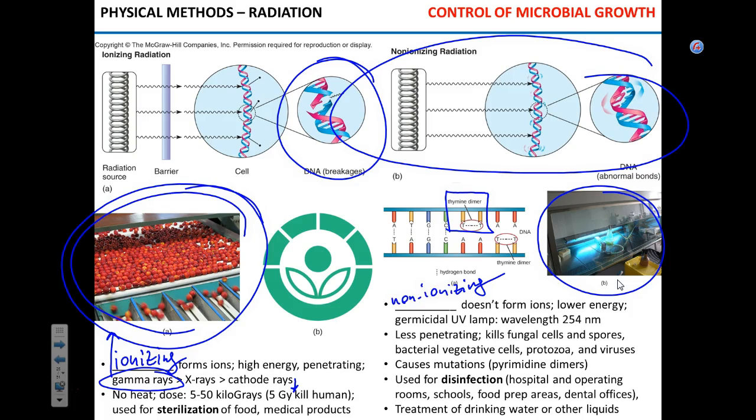You can see on this picture the UV light that is used in the biological safety hoods. After you finished working with, say, bacteria or viruses, okay? Turn on UV light, you close the sash. In the modern hoods, you have to close the sash in order for UV light to work, so you don't burn yourself. And then you go. And you can leave it overnight, and overnight everything gets killed by the UV light inside of that hood. You come next morning, you open it up, turn on the blower, and let it run for 5 minutes.